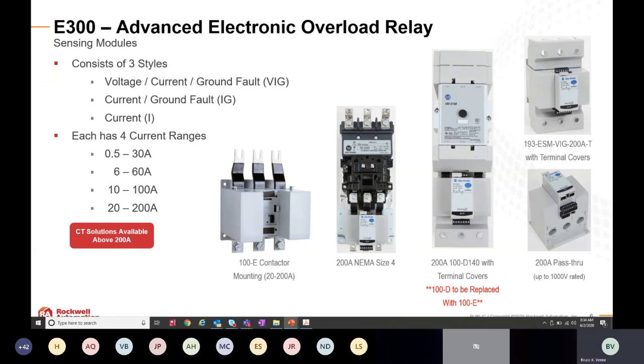There are 4 different current ranges the E300 supports: 0.5 to 30 amps, 6 to 60, 10 to 100, and 20 to 200. Above 200 amps, similar to the E100, you can use external CT configurations with the E300 all the way up to 65,000 amps—very versatile and expandable in terms of the wide range it can support.